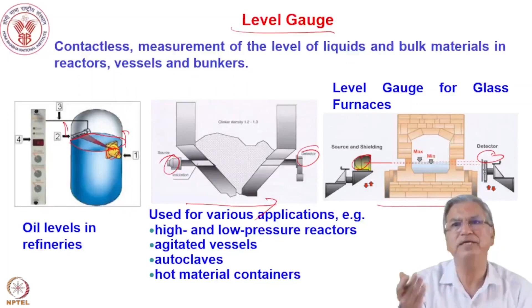Similarly, in mixers there's an uneven level inside, like clinkers, used in the cement industry. You put a source and detector, and from the attenuation of the gamma ray intensity in the detector, you can determine the level of material inside the plant. In a glass furnace, you don't know the level of molten glass from outside, but if you put a source and detector, the attenuation in the gamma ray will be more when passing through molten glass, and less when above the molten glass level. So you can precisely find the level of the glass furnace. These are level gauges; similarly there are density gauges and so on. There are many areas where you can use these radioisotopes.